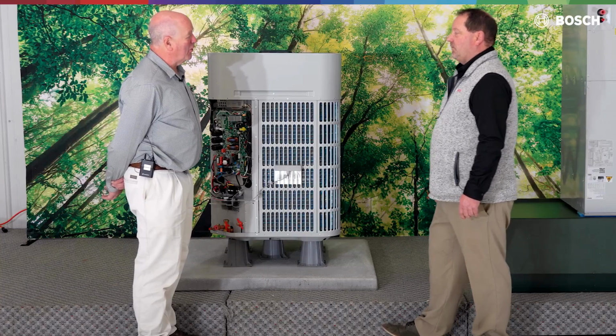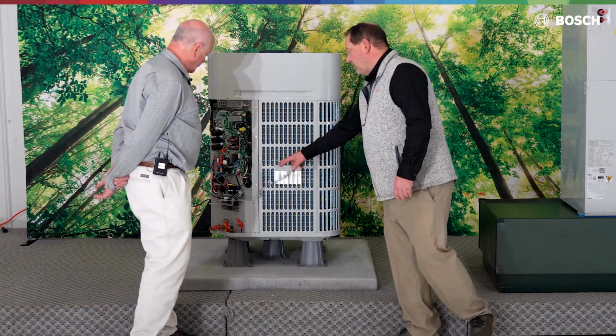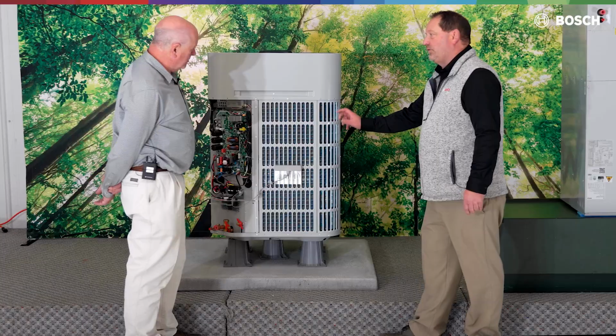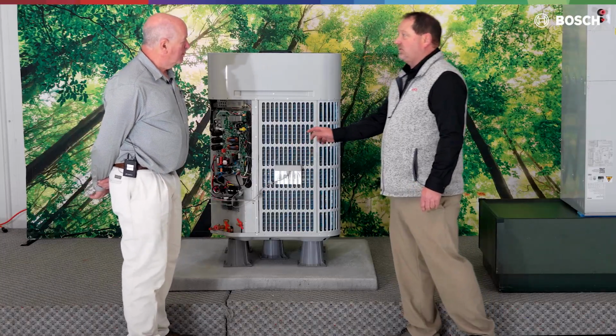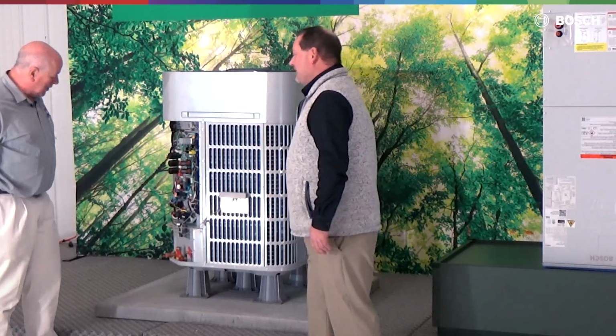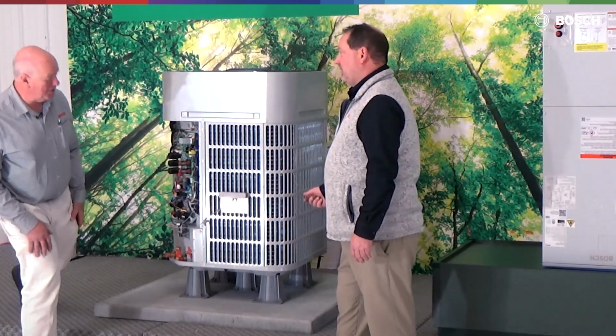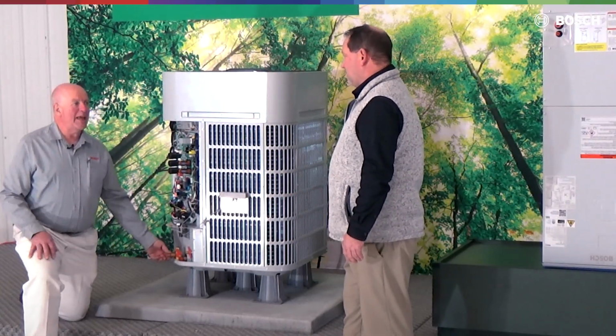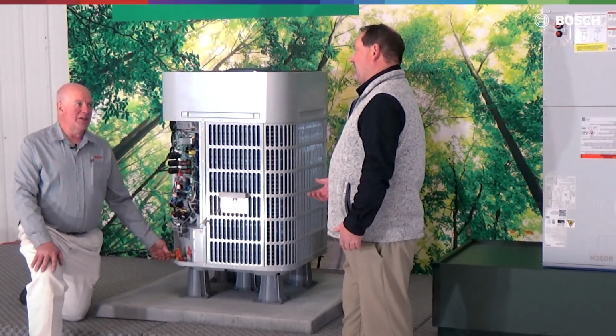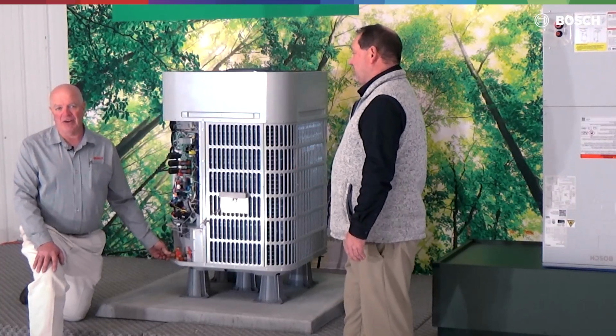That would enhance the performance of that process as well. So earlier we mentioned too that we now approve mechanical type connections. If we're going to go mechanical, my complaint on mechanical fittings is that if you goof up one mechanical fitting, you're going to have to change that service valve, everything we're avoiding.